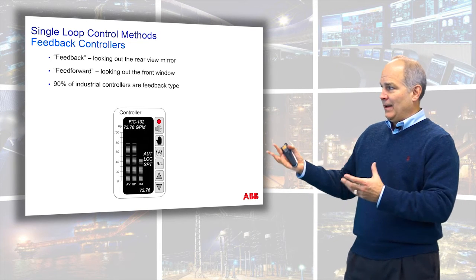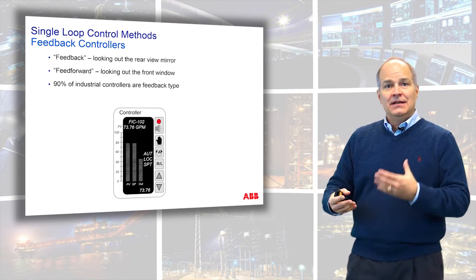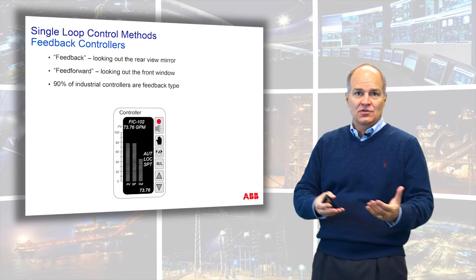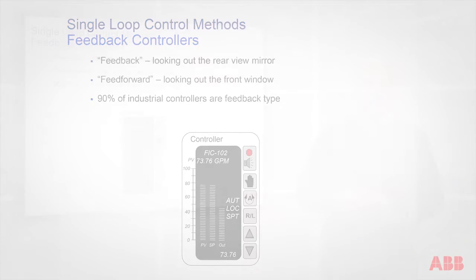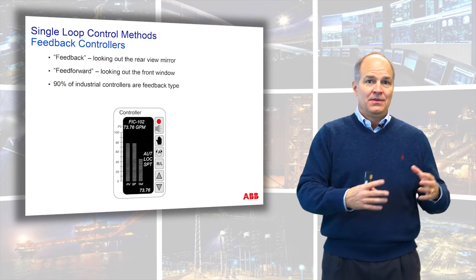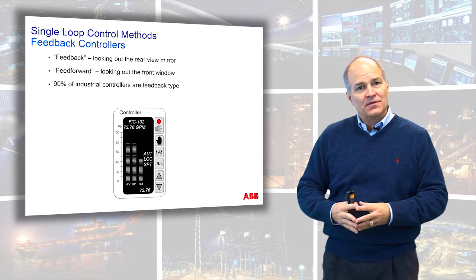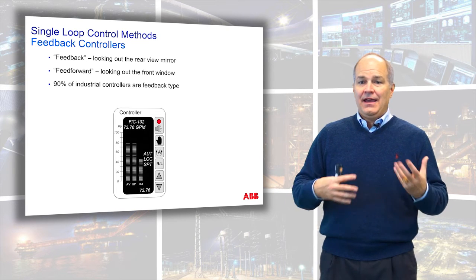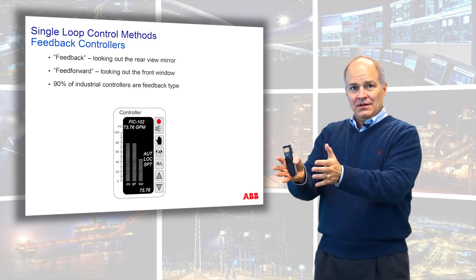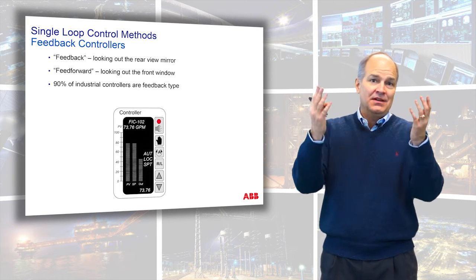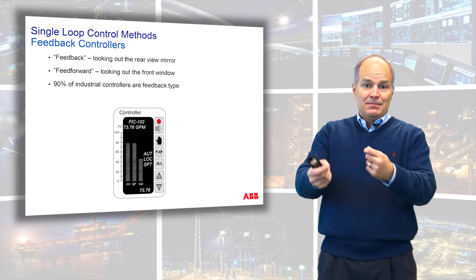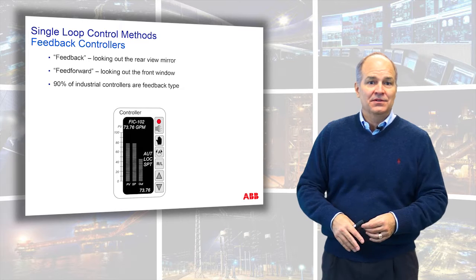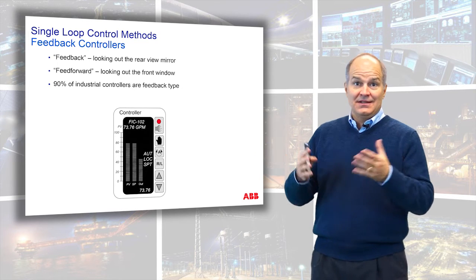Keep that in mind: feedback controllers — proportional, integral, and derivative — are reactive in nature, and that is what defines the control actions and the way you tune them. 95% of all industrial controllers fall into this PID algorithm, yet it's one of the most misunderstood areas. There are a lot of different forms of the PID, different tuning parameters, different units, and you could be very good at one controller or manufacturer and then change to another, put the same numbers in, and blow something up. So it has given tuning and controllers kind of a bad name — it's like a black art, you're just throwing numbers in until you get it to work.